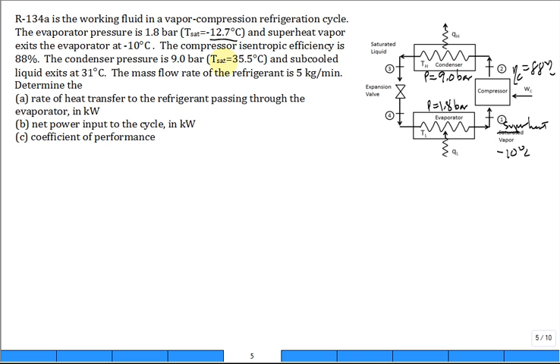The corresponding saturation temperature is 35.5 degrees C for that pressure of 9 bar. Now it exits sub-cooled liquid, not saturated, sub-cooled liquid at 31 degrees C. So if it exited as saturated liquid, it would come out 35.5 degrees C, but it comes out 31.